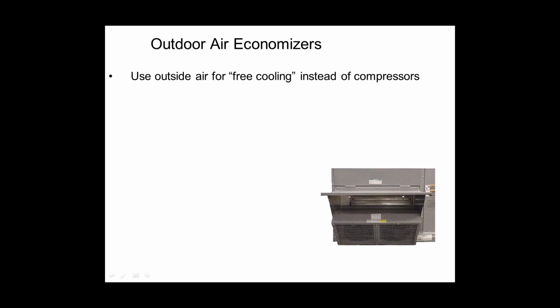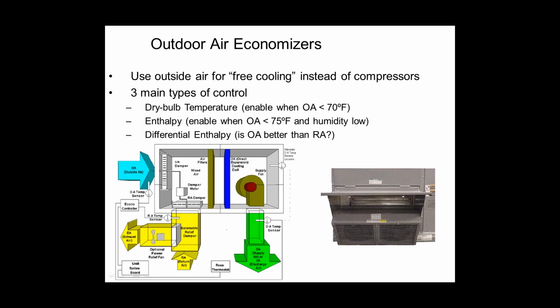So instead, we put an operable window inside your air handling piece of equipment or your rooftop unit. And whenever we want to cool the space and it's cool enough and or dry enough outside, we will open that window and suck fresh air into the building to free cool it, hopefully without having to even energize any compressors. We'll talk about that. There are 3 main ways that we control this, specifically in our region of the country anyway. The first of which is dry bulb temperature.